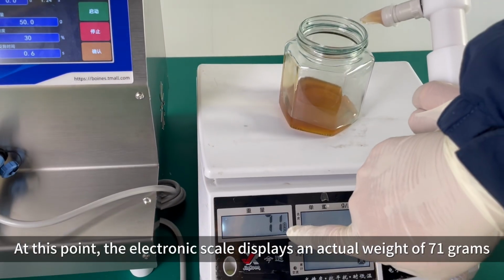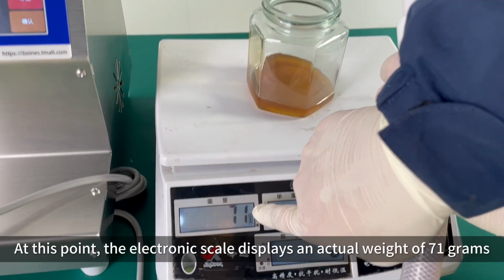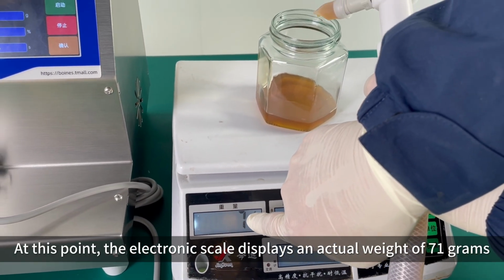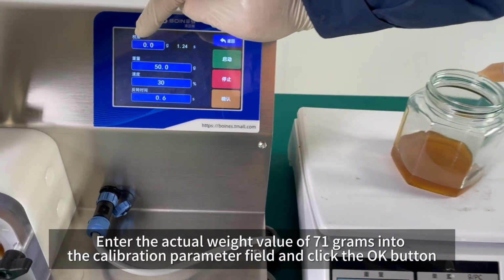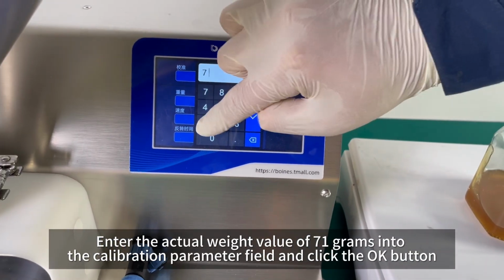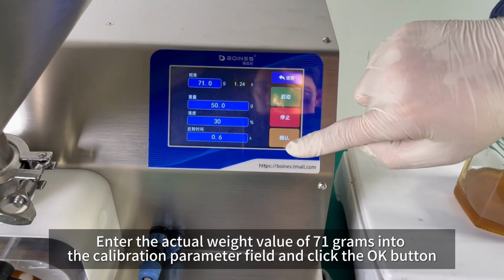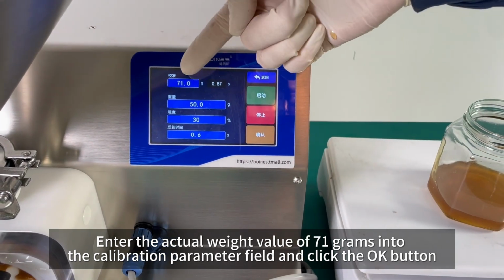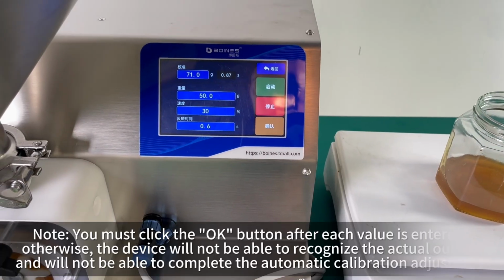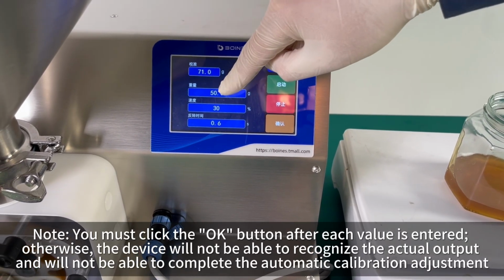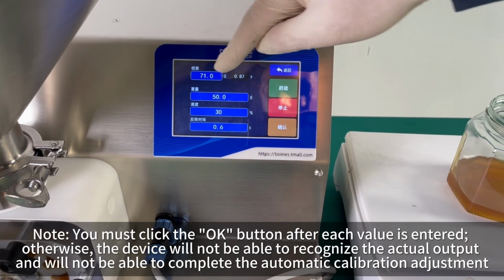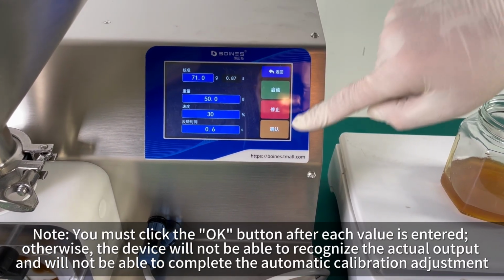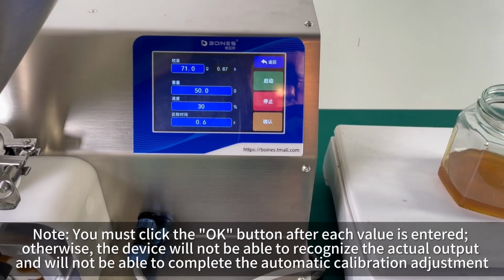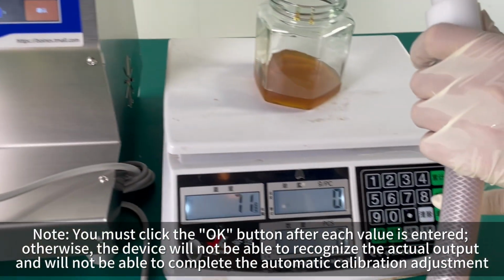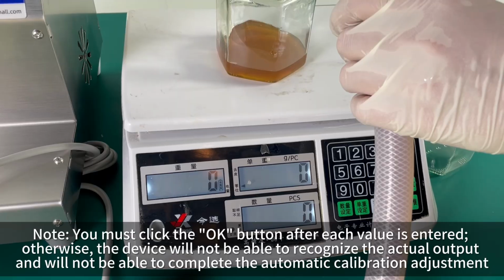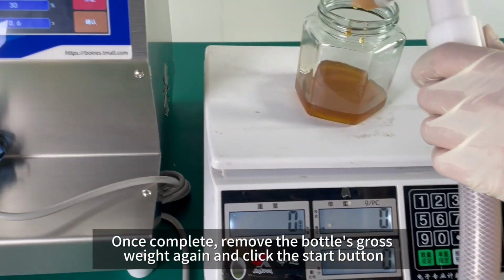At this point, the electronic scale displays an actual weight of 71 grams. Enter the actual weight value of 71 grams into the calibration parameter field and click the OK button. Note, you must click the OK button after each value is entered. Otherwise, the device will not be able to recognize the actual output and will not be able to complete the automatic calibration adjustment. Once complete, remove the bottle.